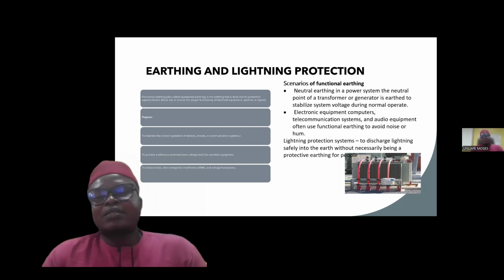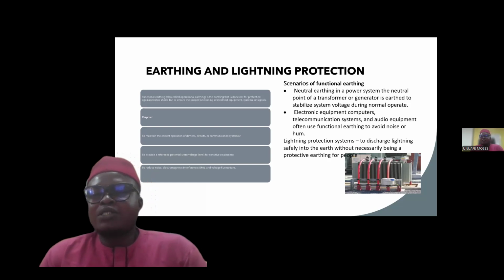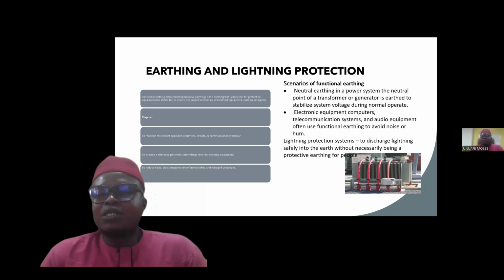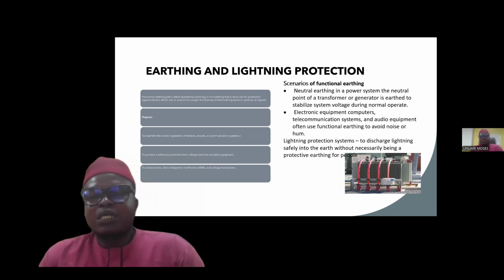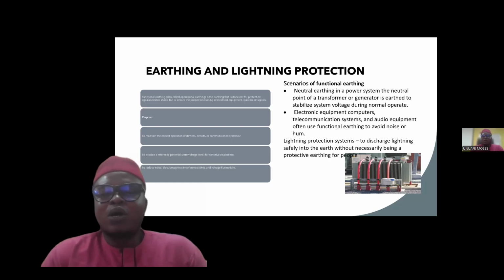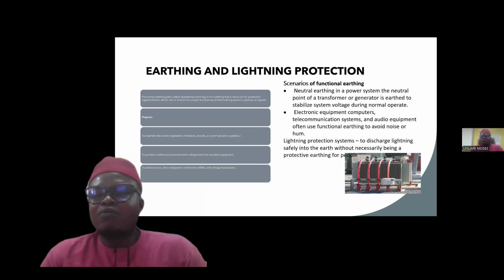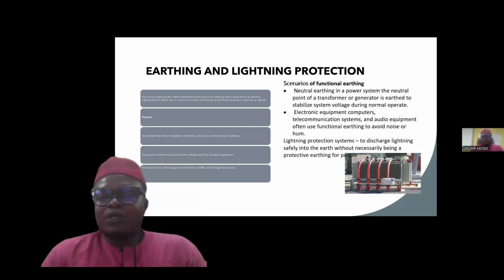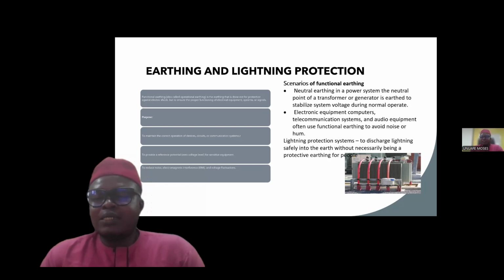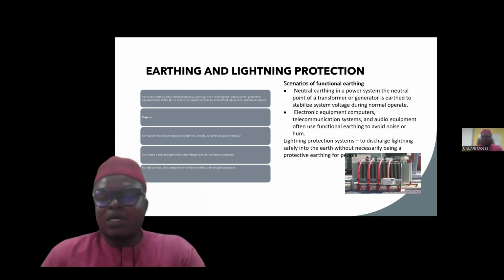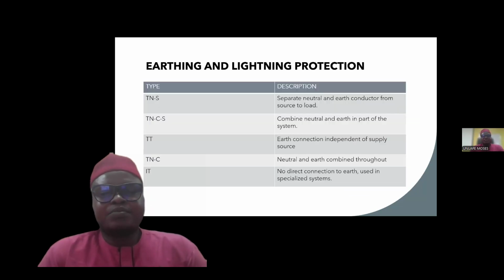Now, let's look at a scenario of functional earthing. It is neutral earthing in a power system, where the neutral point of a transformer or generator is earthed to stabilize the system voltage during normal operation. This is also applicable to electronic equipment, computers, telecommunication systems, and audio equipment, which often use functional earthing to avoid noise. If you look at the slide, there is a picture of a transformer whose neutral is well earthed to the ground. This is an example of functional earthing.